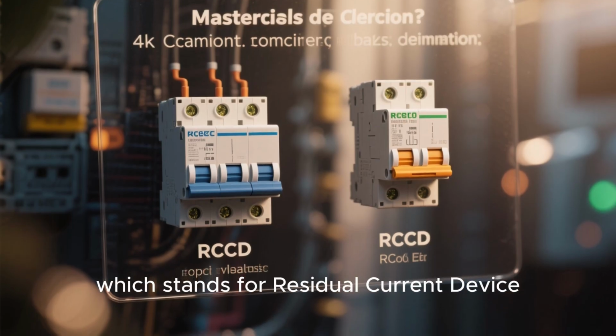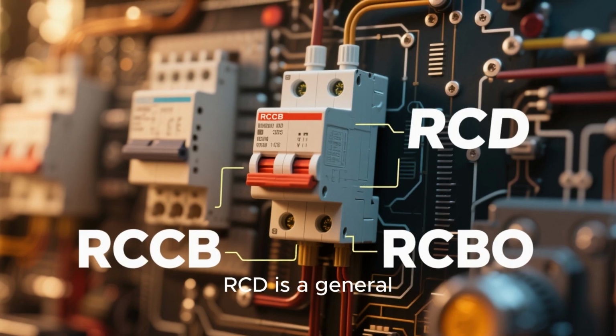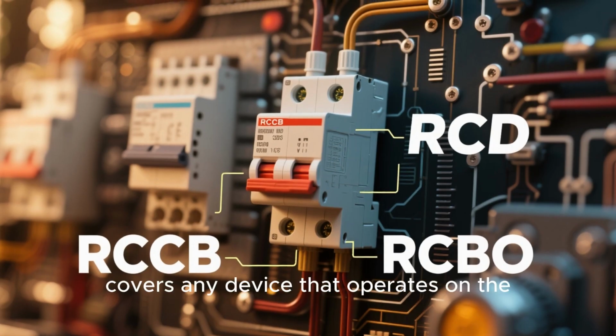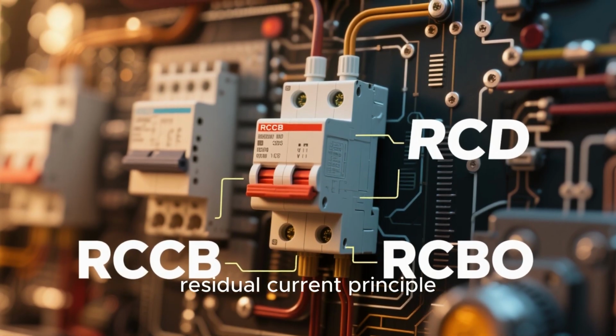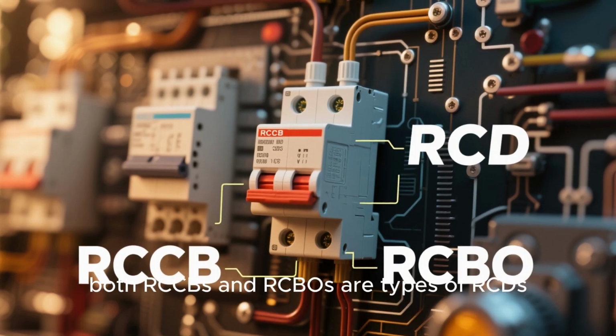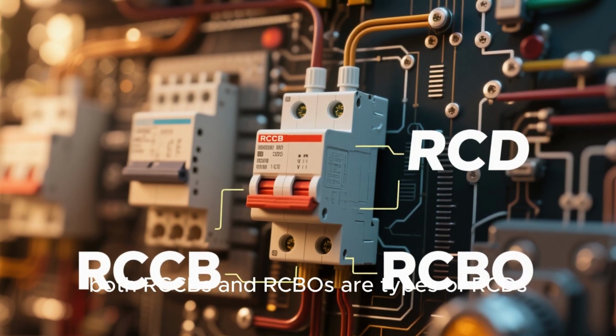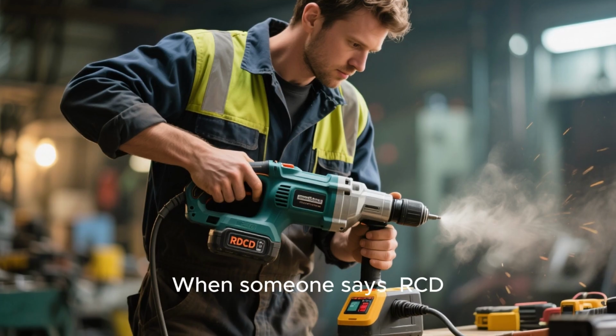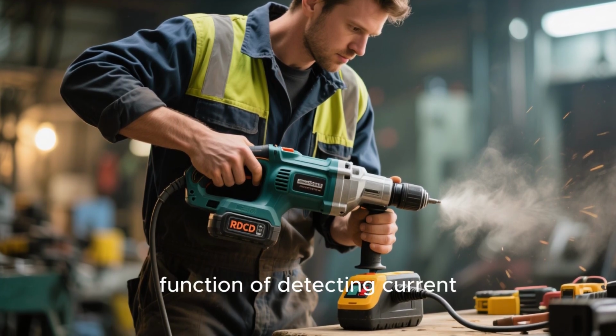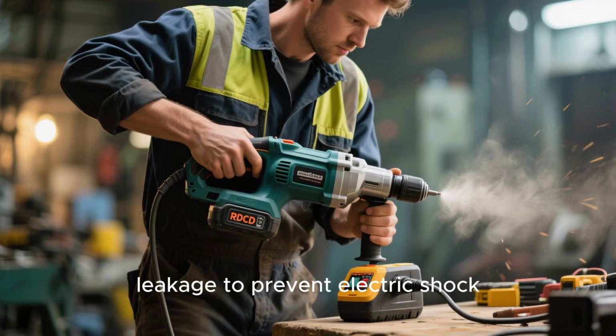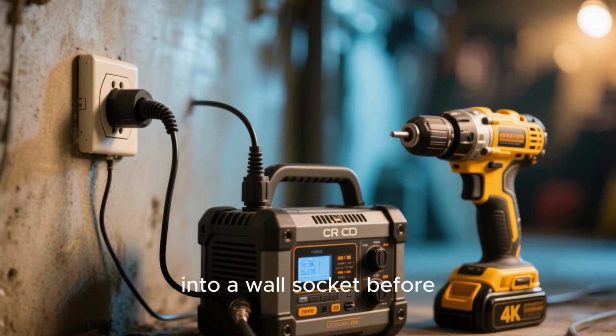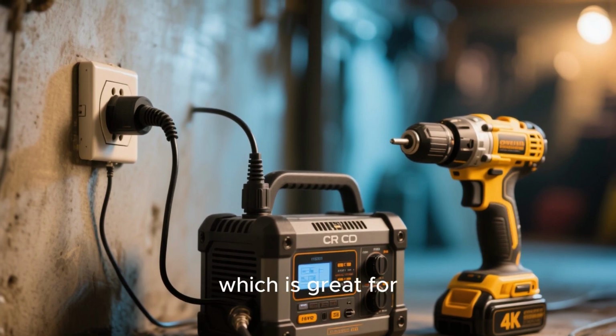You might also hear the term RCD, which stands for Residual Current Device. RCD is a general, umbrella term that covers any device that operates on the residual current principle. So, both RCCBs and RCBOs are types of RCDs. When someone says RCD, they are talking about that life-saving function of detecting current leakage to prevent electric shock. You can even get portable RCDs that you plug into a wall socket before plugging in an appliance, which is great for using power tools outdoors.